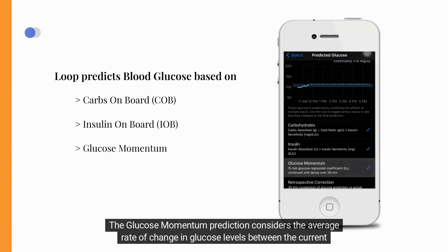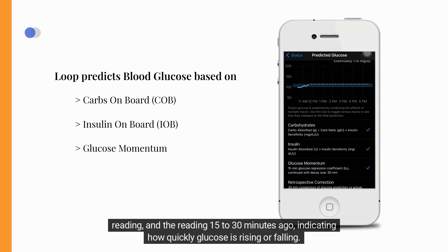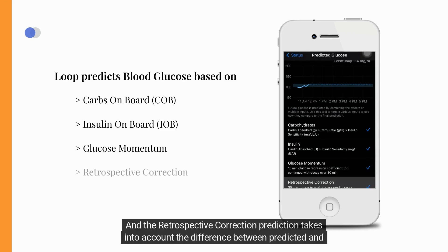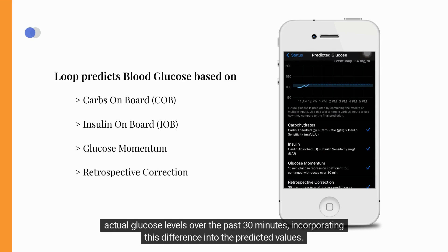The glucose momentum prediction considers the average rate of change in glucose levels between the current reading and the reading 15 to 30 minutes ago, indicating how quickly glucose is rising or falling. The retrospective correction prediction takes into account the difference between predicted and actual glucose levels over the past 30 minutes, incorporating this difference into the predicted values.